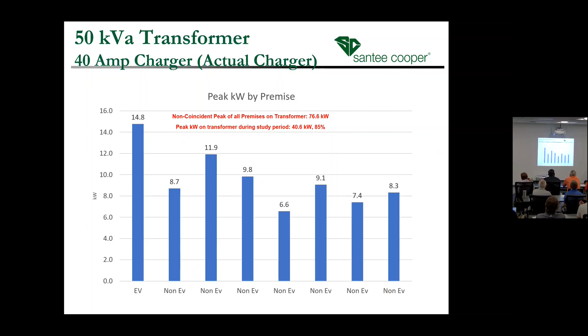So the non-coincident peak on this transformer is 76 kW. Luckily, the coincidental peak over that 2-month period was only 40.6 kW. So for this example, if you were to add another 9.2 kW because someone upsized or another customer got a 40 amp station and started charging at the same time, you still wouldn't hit capacity. I think you'll see that a lot with 50 kVA transformers - you're bumping up against capacity, compared to 25 kVA where you overshoot it pretty quickly. And then with 75 and 100, the concern is probably even less.